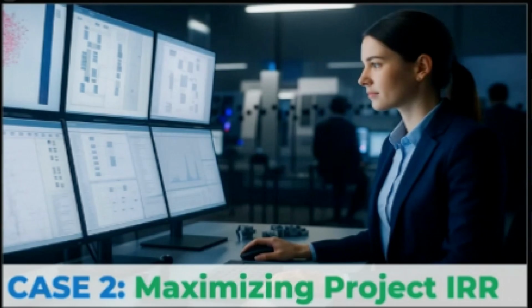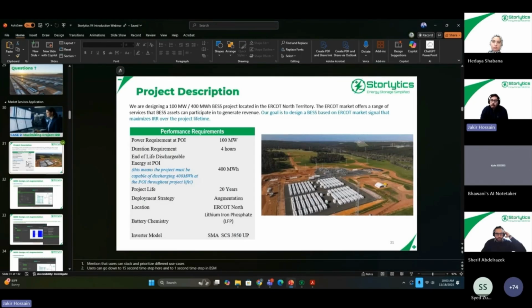of augmentation. And when you are doing augmentation, the question that often comes up is, what should be your augmentation strategy? Are you going to go with AC augmentation or DC augmentation? How often should you do your augmentation? How frequently? What should be your initial overbuild duration? That kind of question is impactful because the amount of augmentation you do, when you do it, and how much capacity you add, all add to your overall project CapEx and OPEX as well. And that eventually impacts your project IRR.